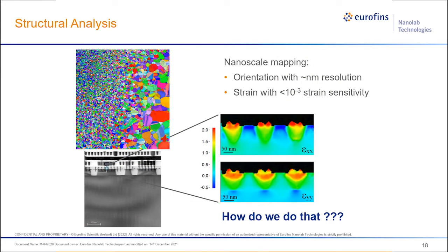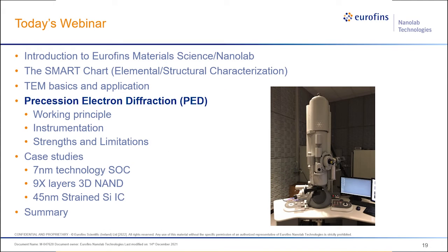Besides chemical analysis, TEM can also provide structural information. For example, it can provide grain orientation mapping — just like EBSD but at higher resolution — and strain mapping at nanometer resolution with 10⁻⁴ strain sensitivity. The technique that enables this is precession electron diffraction, PED, which brings us to the next part of the talk.